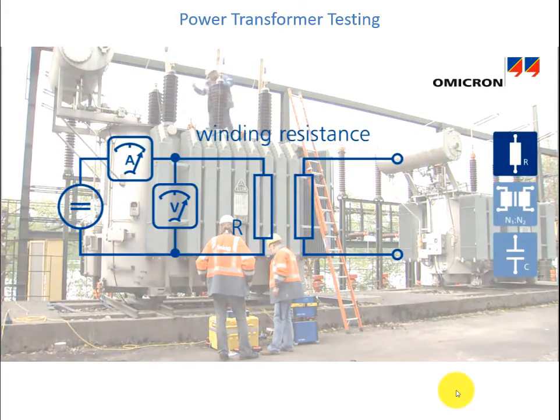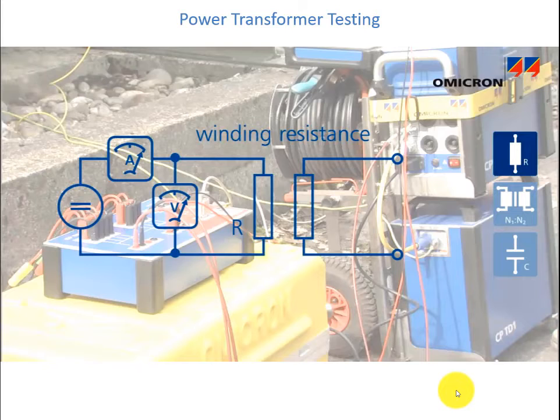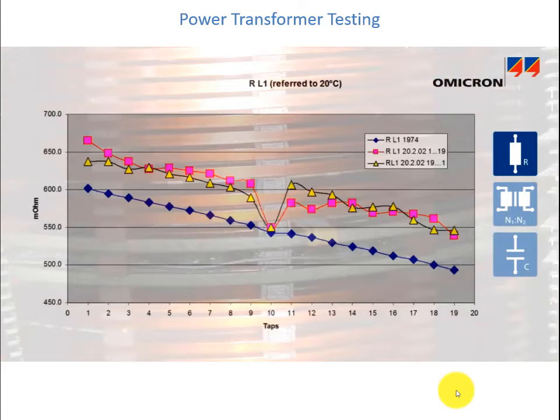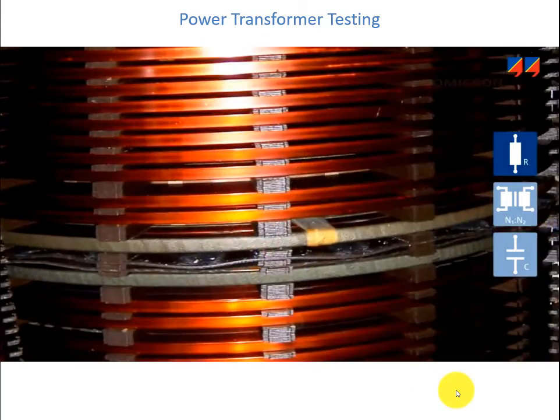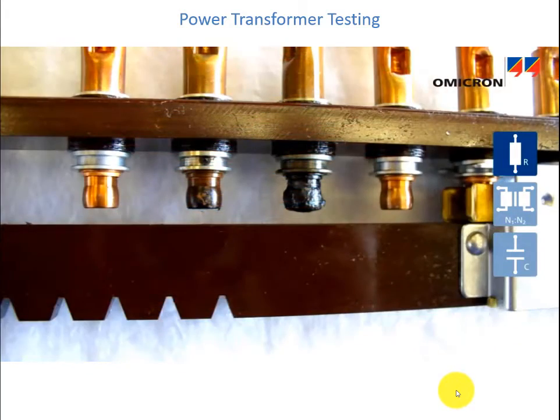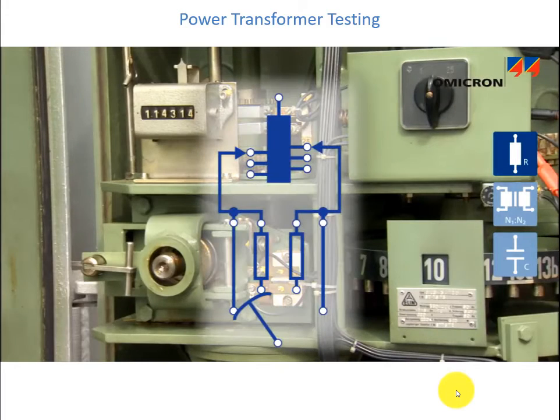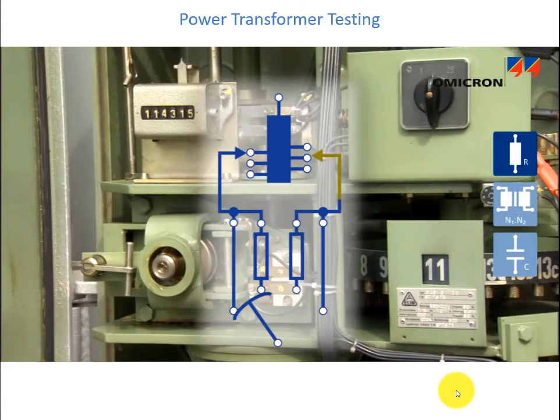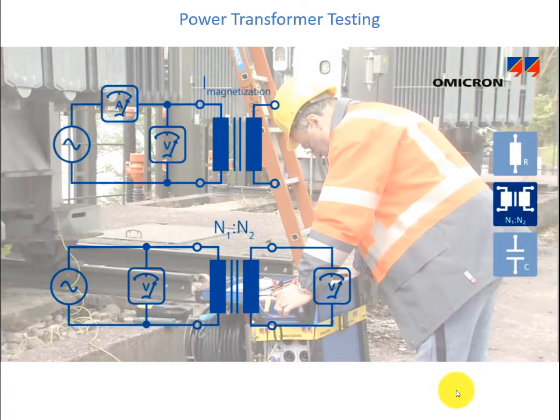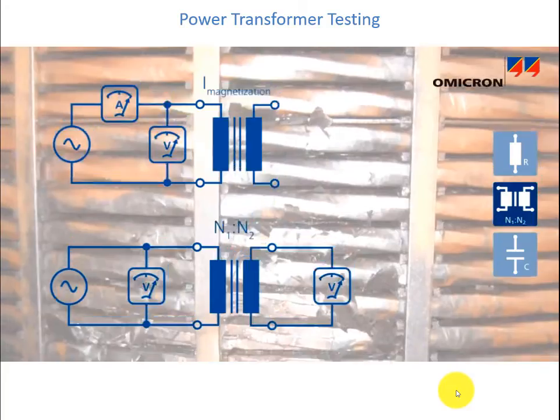Measuring the winding resistance and comparing it to factory measurements allows possible winding damage to be identified, for instance winding short circuits or contact problems of the winding leads or the tap changer. Measuring ratio and magnetization current helps to identify short circuits between winding turns.